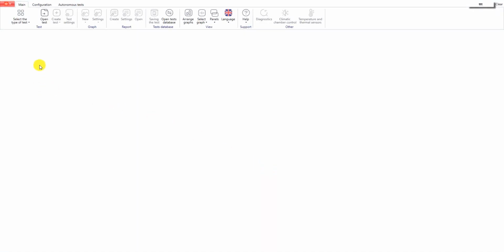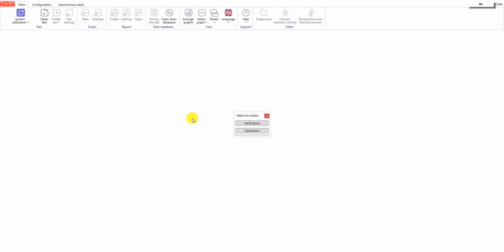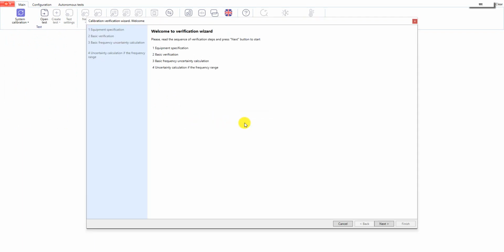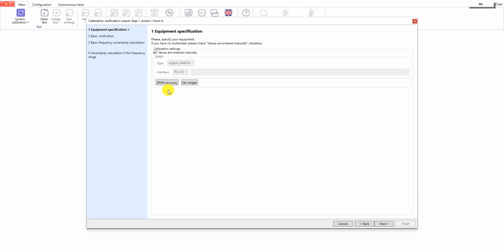Now let's open our TestUp software and go to controller calibration test. Here we need to select verification. The first window we see is an informational one. Here we see the list of all measurement steps. After that we click next and we need to specify our equipment.